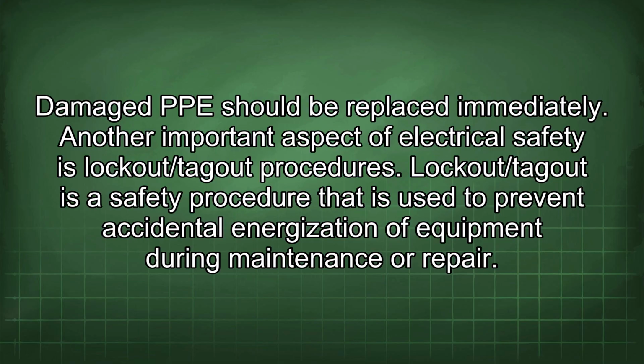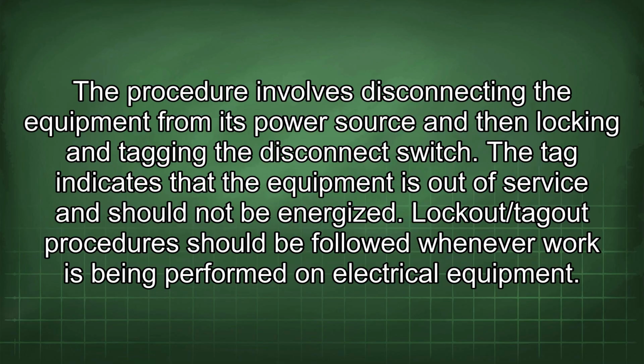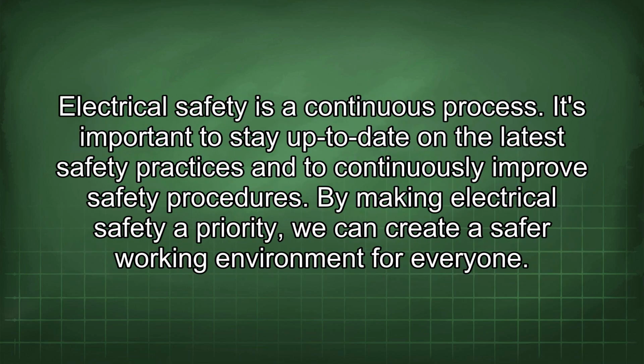Another important aspect of electrical safety is lockout/tagout procedures. Lockout/tagout is a safety procedure that is used to prevent accidental energization of equipment during maintenance or repair. The procedure involves disconnecting the equipment from its power source and then locking and tagging the disconnect switch. The tag indicates that the equipment is out of service and should not be energized. Lockout/tagout procedures should be followed whenever work is being performed on electrical equipment. Electrical safety is a continuous process. It's important to stay up to date on the latest safety practices and to continuously improve safety procedures. By making electrical safety a priority, we can create a safer working environment for everyone.